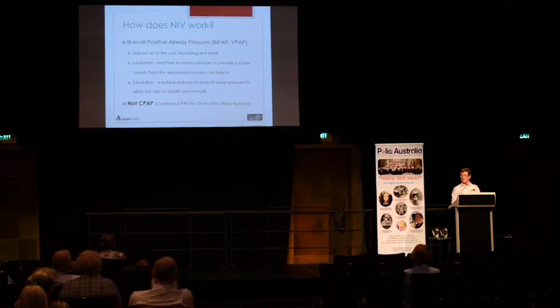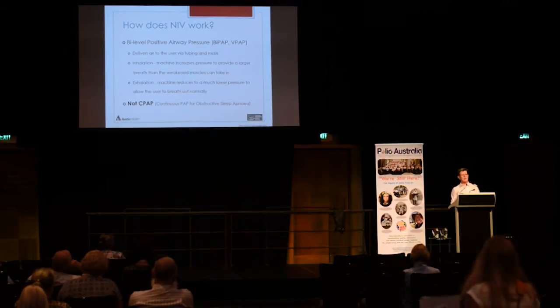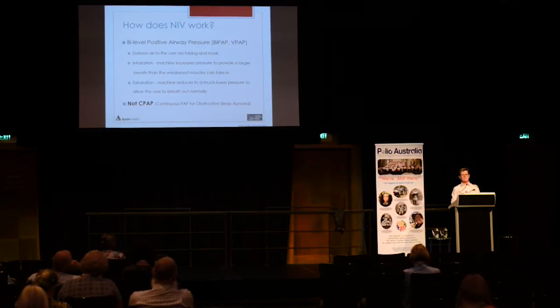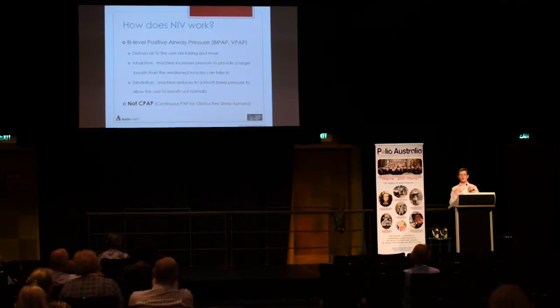How does it work? It delivers air to the user via a mask and tubing, or in some cases by a tracheostomy. When you breathe in, the machine follows you and delivers air until you start breathing out. So the pressure goes up as you breathe in, and when you begin breathing out, the pressure drops down to allow you to exhale properly. Again, I'll say non-invasive ventilation, CPAP is not non-invasive ventilation. What CPAP does is blow a continuous amount of air, a low flow of air, into the upper airway to hold your throat open so you can get a normal breath by yourself. But bilevel ventilation helps you breathe or breathes for you, whatever is required on a breath-by-breath basis.